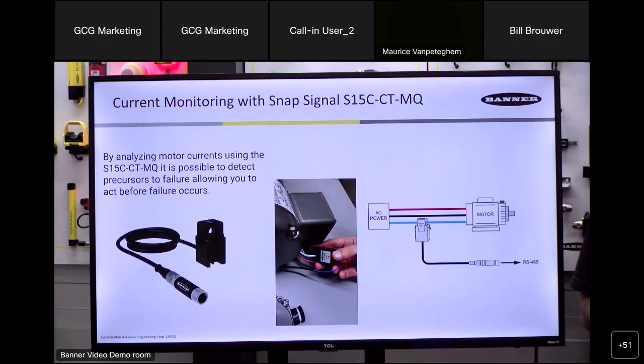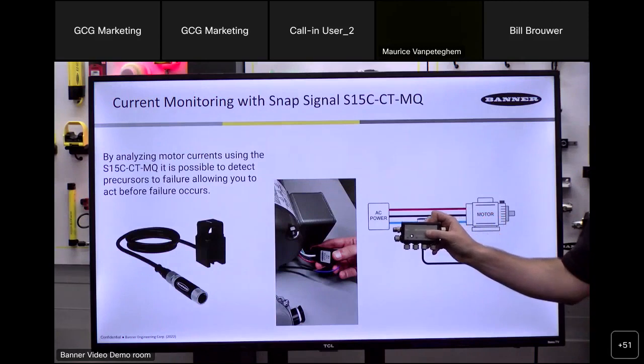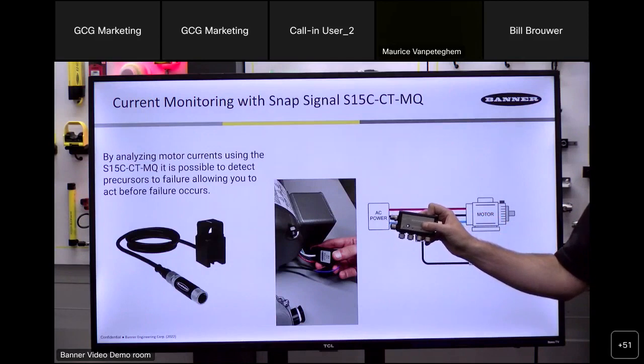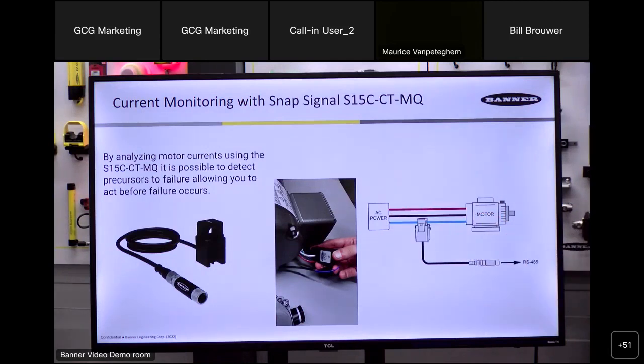Check out Banner's S15C-CT-MQ, which can be used with the DXMR90 industrial controller to continuously monitor multiple motor currents. Once you know the normal current draw during operation, by tracking the data over time you can determine appropriate current limits and even set up simple text or email alerts in a cloud-based platform, or send this data directly to a PLC, HMI, or SCADA system.